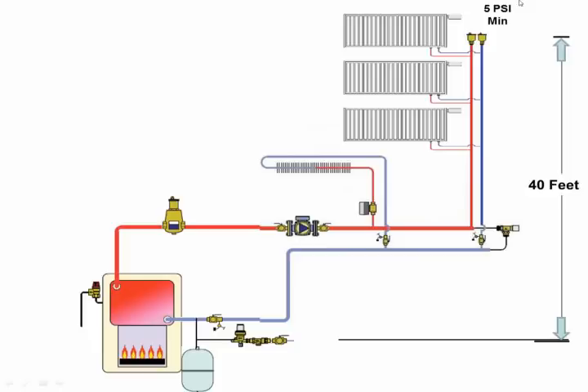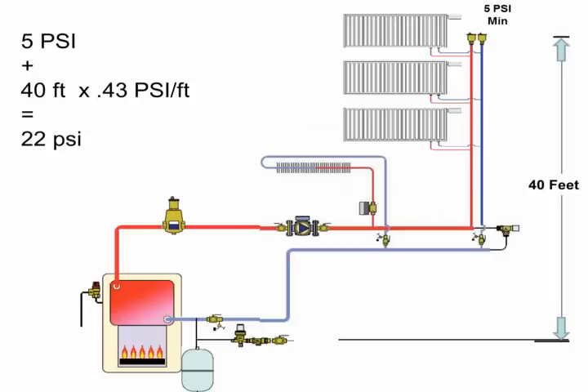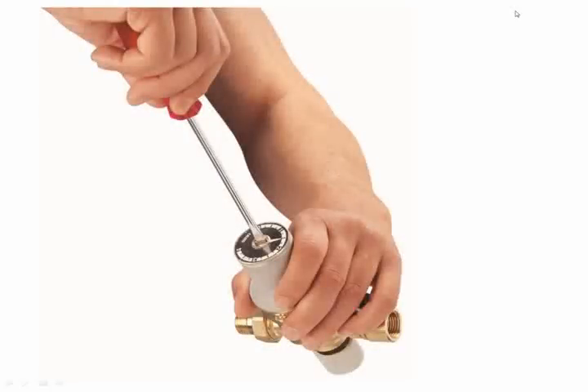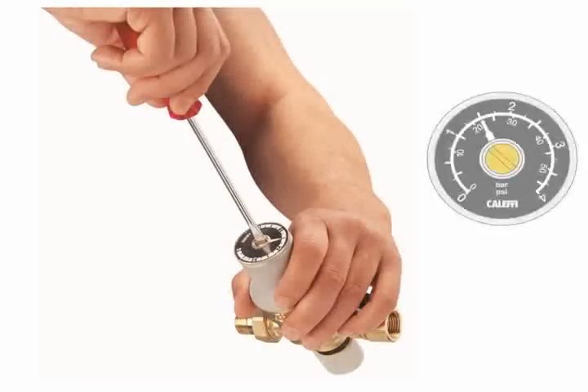This is where you want to put air vents. And automatic air vents like to be operating under pressure. To make sure they have positive pressure, in the case of Caleffi, like 5 psi minimum, 10 is okay too. In fact, you can go as high as you want as long as you stay under the maximum operating pressure. So as the designer, to make sure you get 5 psi at the top of your system, down here where you pressurize the system, what would you do? Well, you would designate that it gets pressurized at 22 psi. That would create 5 psi up here.